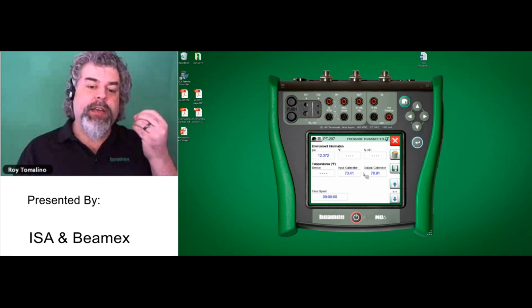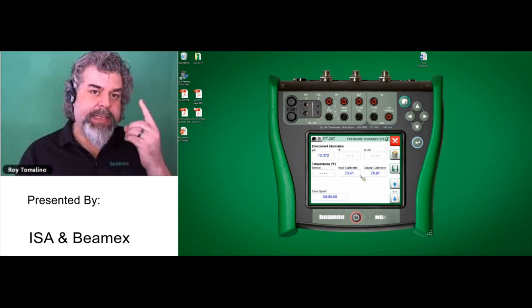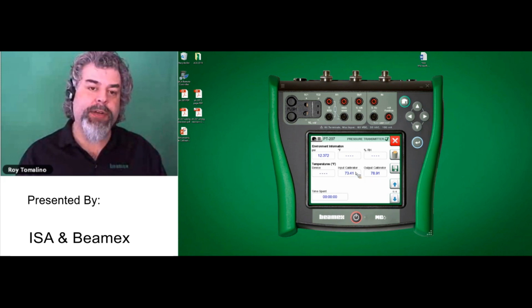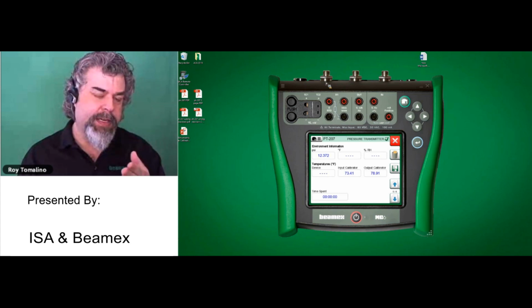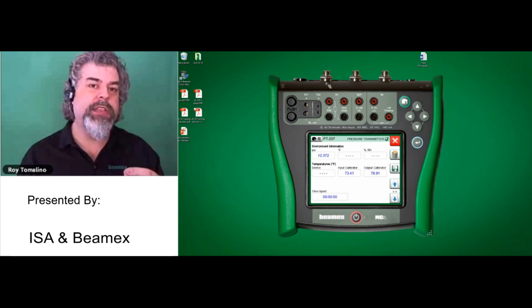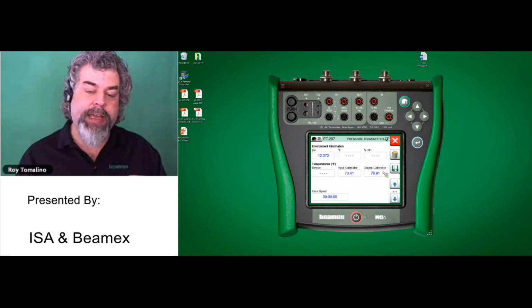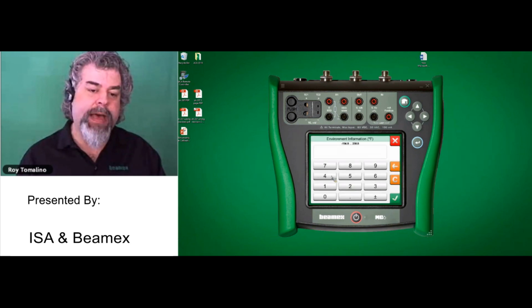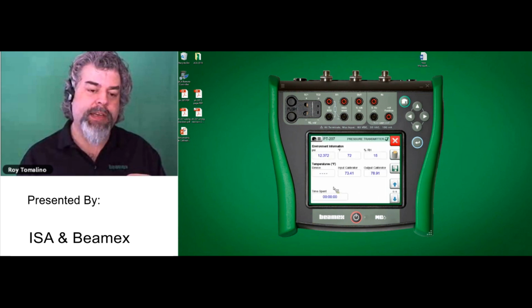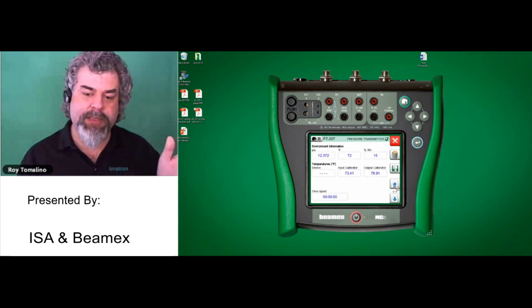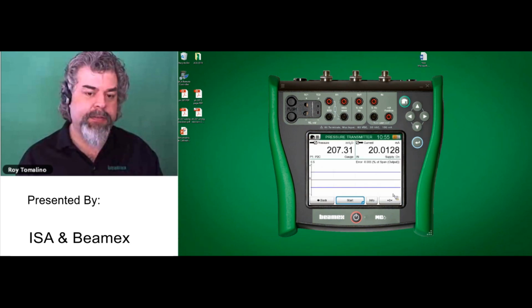Now, there are temperature values that are recorded by the calibrator automatically, and that's the input calibrator. That's the temperature of that pressure module specifically, because this is temperature compensated within the calibrator itself. And the output calibrator is where we're measuring current. I'll put in the same values: 72 is my ambient temp, and I'll put in 15% humidity. The actual temperature of the device, I'm leaving that blank. I'll save this as both as found and as left.